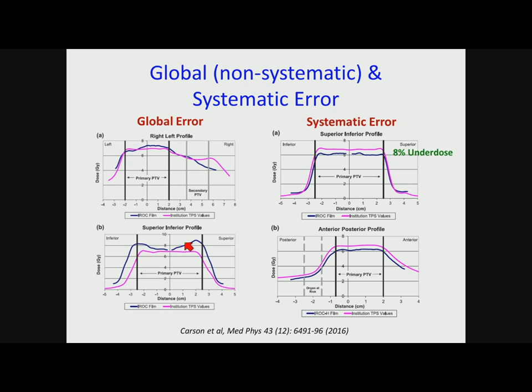Cause of failure, some treatment planning system, Linac combinations did better than others. Most detectable errors systematic and dosimetric, so that is one thing they found out from this study. Cause of failure included incorrect data entry into the treatment planning system, so things were wrong. The data went in like a garbage in, garbage out, wrong PDDs. Inexact beam modeling, MLC leaf modeling, which is a big one. Software and hardware failures, inexperienced qualified medical physicists and dosimetrists, IMRT implementation incorrect, gross setup errors.